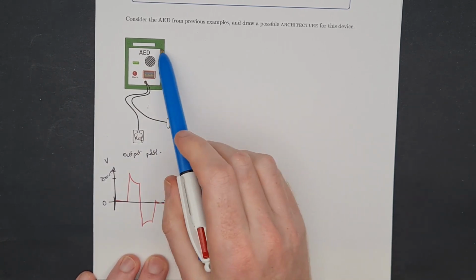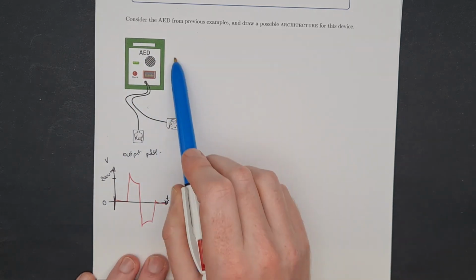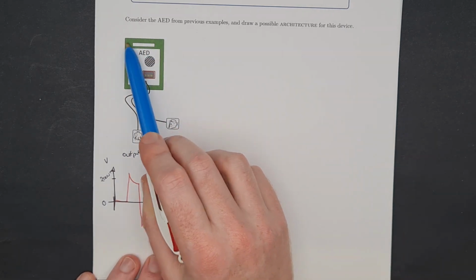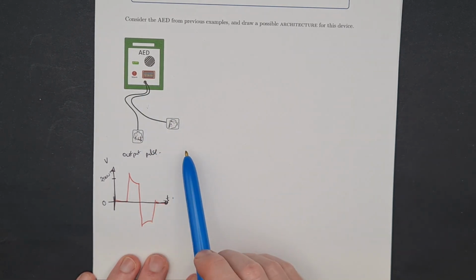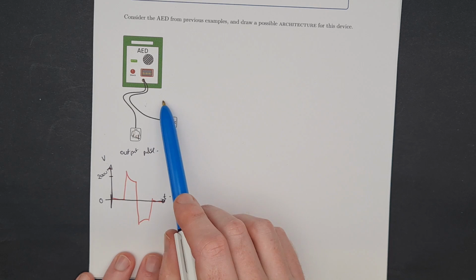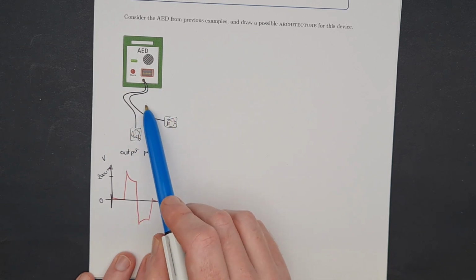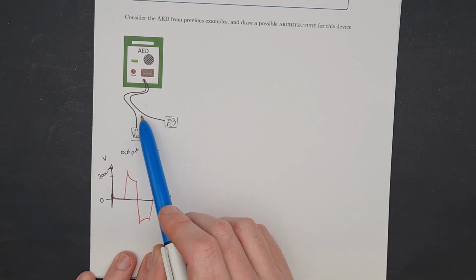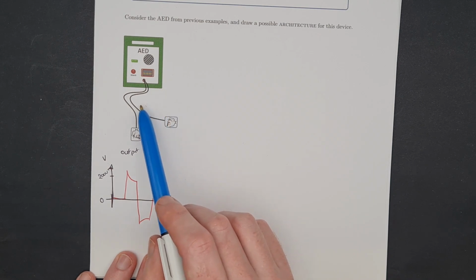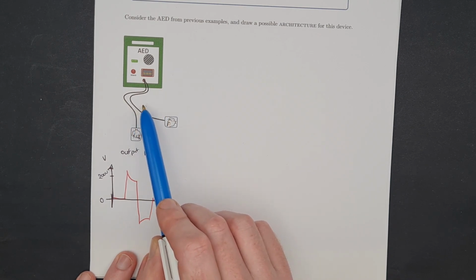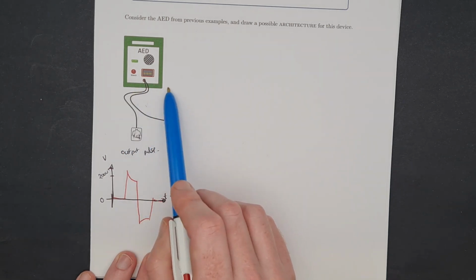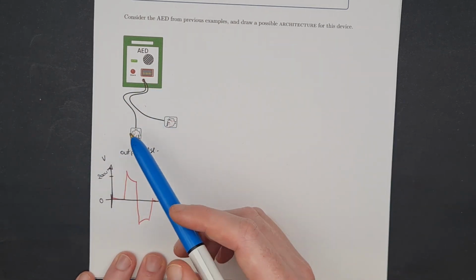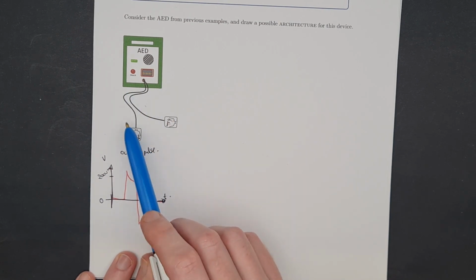Okay, so the architecture we're going to draw out is going to be a programmable electromechanical system. It's going to contain mechanical components, electronic components, software components. It's going to contain an external system, which is going to be these electrode pads. Why I say system is because you're basically implying that they're a separate assembly that's going to be tested at their system level, because you can test each cable assembly as well, independent of the AED, and you can test the AED as a system.